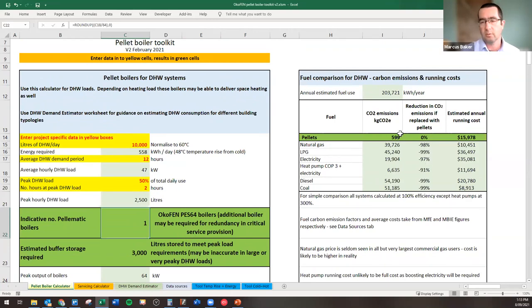And I think really importantly as well, there's a live fuel comparison calculator over here, so you can see, if we increase that to 15,000, all the numbers change. And it gives you the CO2 emissions of it using pellets, natural gas, LPG, electricity, a heat pump with a COP of 3, diesel and coal. And you can see that compared to pellets, there's a pretty significant CO2 burden.